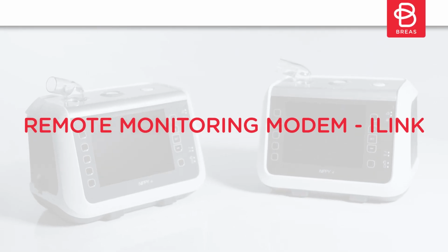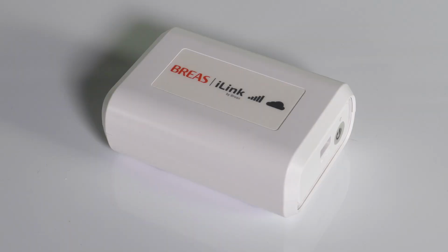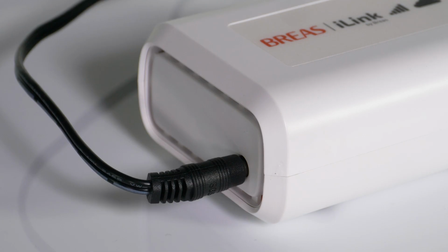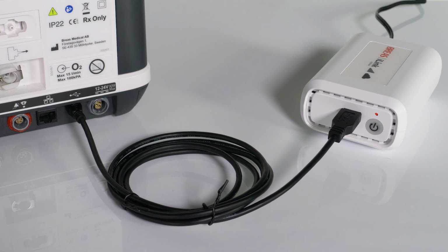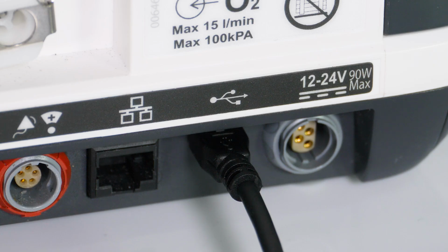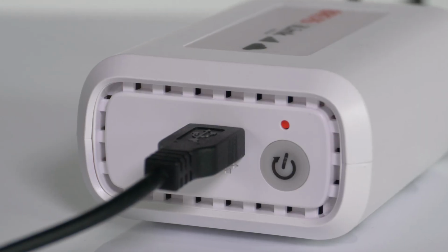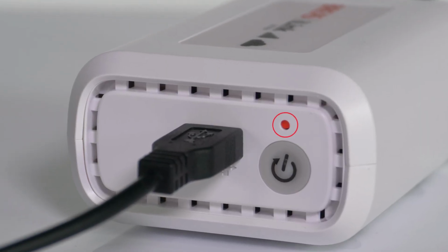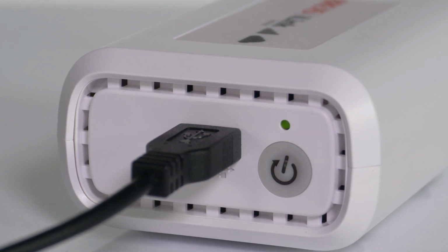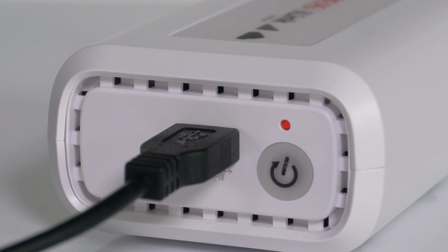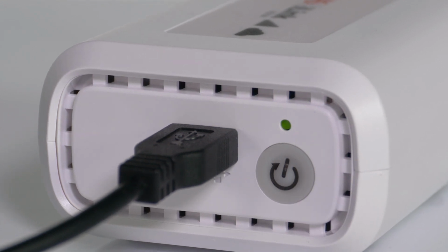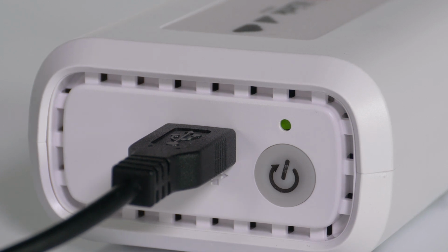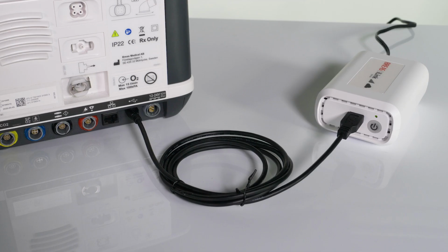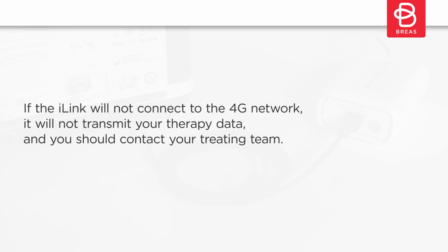Remote monitoring modem, iLink. You may have an iLink 4G modem accessory, which is required to stream the ventilator data to the hospital treating team. The iLink needs to be connected to the mains power and also to the Nippy 4 via a micro USB cable. When attached to the mains, the iLink will attempt to connect to the cellular network. When it powers up, it will display a steady red light for about 15 seconds, and then start scanning for a 4G signal by showing a flashing alternate red and green light. If successful at connecting to the network, the LED will show a steady bright green light for about 15 seconds, before dimming. If the iLink will not connect to the 4G network, it will not transmit your therapy data, and you should contact your treating team.